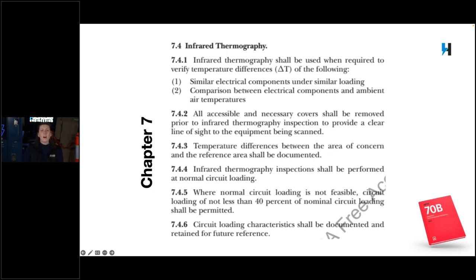Infrared thermography is supposed to tell you where there's a difference in temperature. If something has a similar load in a similar environment with the same ambient air temperature, its temperature should be very similar as well. If it's not, that could be an indication that something is wrong, that it's not operating the way it was designed to.